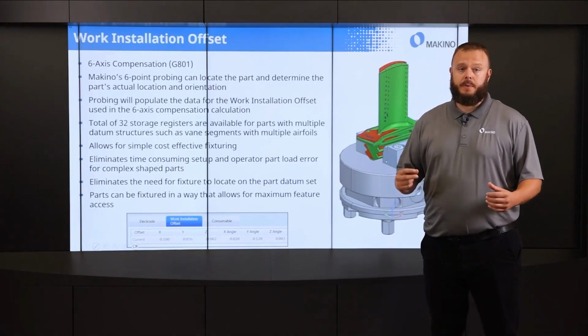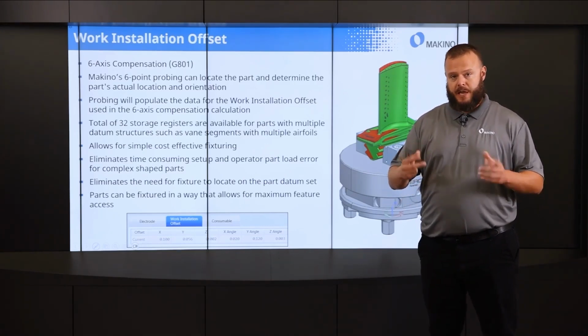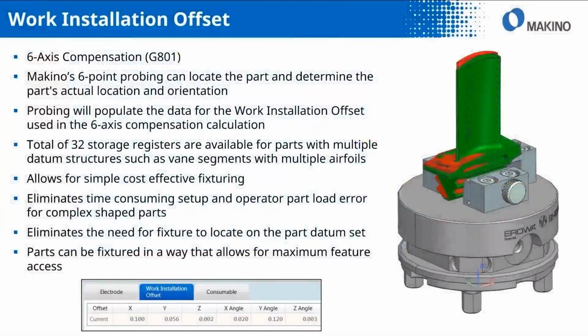The X angle being the deviation about the X axis, the Y angle being about the Y axis, and Z angle being about the Z axis. So with this also we have a total of 32 storage registers, and this helps with parts that have multiple part datum structures, like a vane segment with multiple airfoils. And so the benefit of all this wrapped together with the 6-point probing and the compensation is it allows for simple, cost-effective fixturing. So basically you don't have to fixture or locate using the fixture anymore.